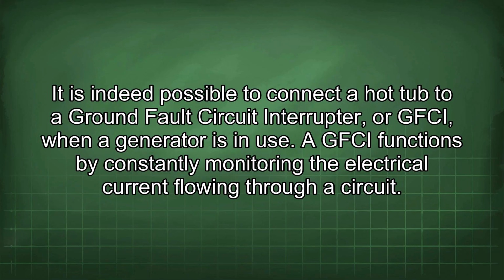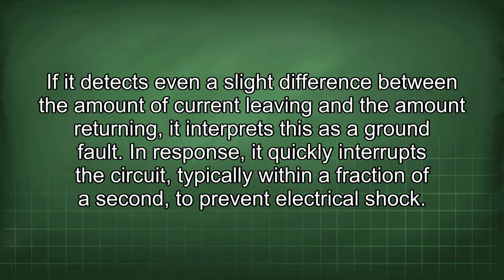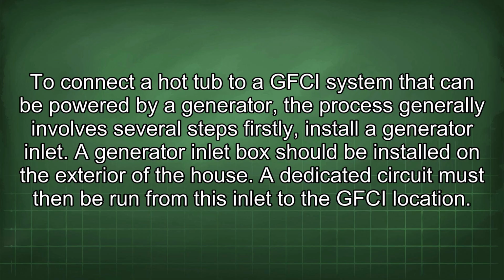It is indeed possible to connect a hot tub to a ground fault circuit interrupter, or GFCI, when a generator is in use. A GFCI functions by constantly monitoring the electrical current flowing through a circuit. If it detects even a slight difference between the amount of current leaving and the amount returning, it interprets this as a ground fault. In response, it quickly interrupts the circuit, typically within a fraction of a second, to prevent electrical shock.